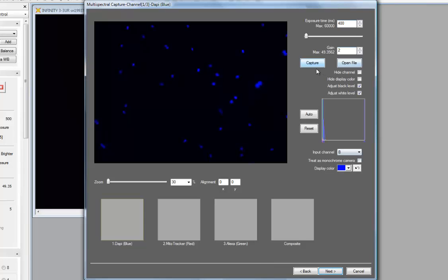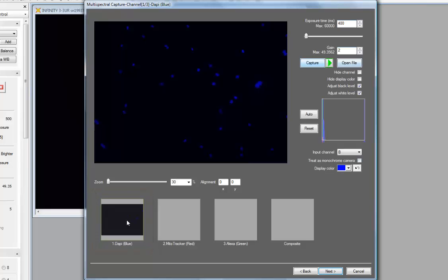And now, to quickly go through a capture sequence, I'm just going to make sure I'm on the correct filter cube. So I'm going to start with my DAPI here, my blue channel. Noticing that my input channel from this color camera is set to the blue channel. I'm going to open the shutter on my microscope, see the results appear on the screen, and quickly click the capture button. As soon as the image is captured, it appears down here in my thumbnail, and I can close my shutter.